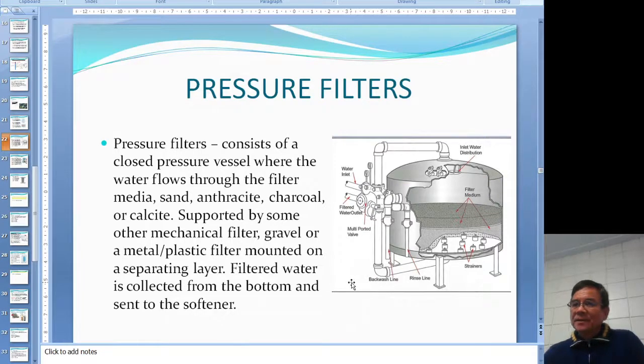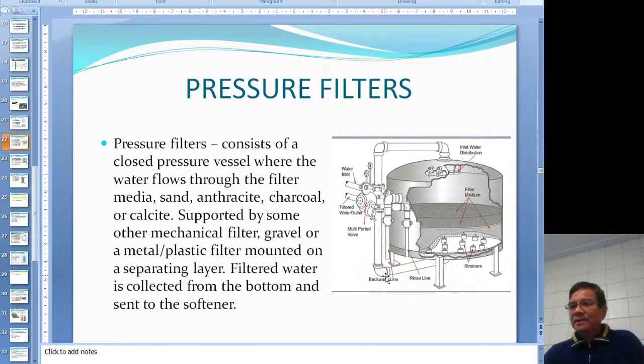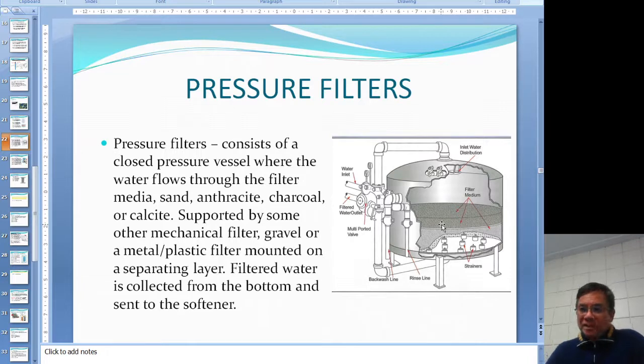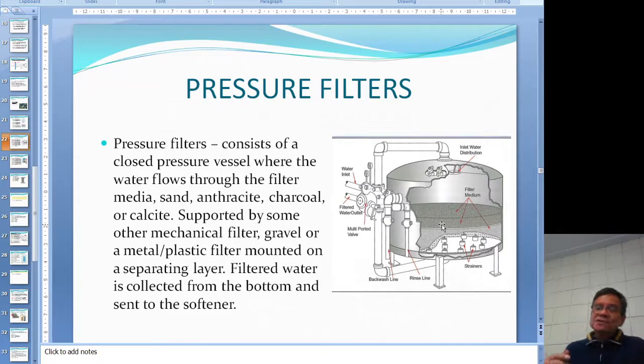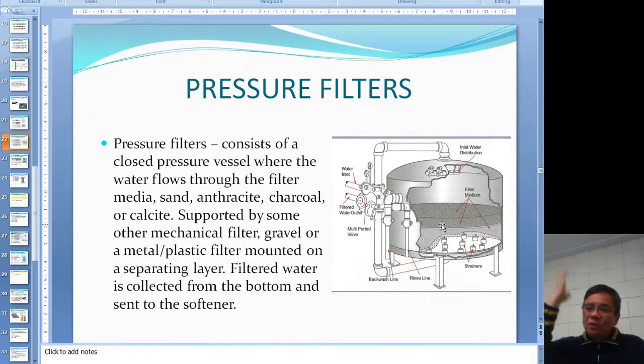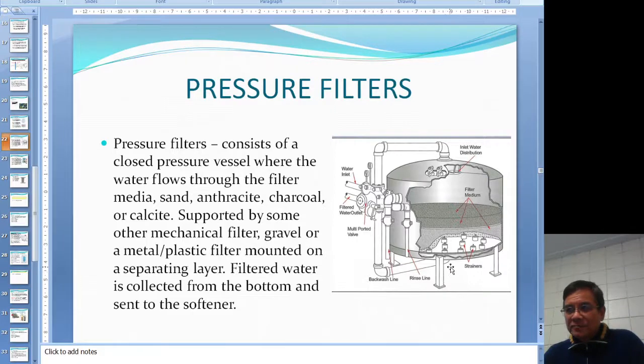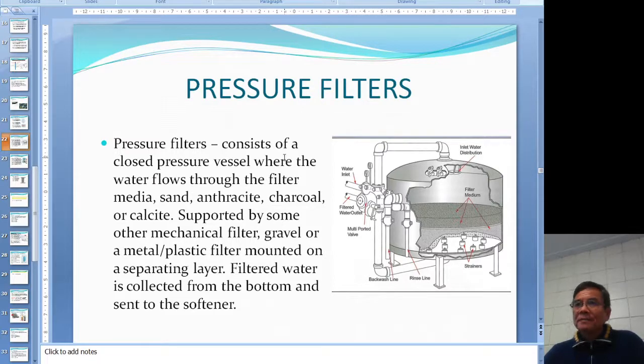The water comes in from the top, goes through the filter, collects at the bottom, and comes out there to the softener. After running for a while, the filter layer collects lots of dirt. To clean it you backwash - put water in from the bottom going up to push the lighter material down the drain. This process is called backwash or reverse flow - it removes all the dirt and organic material down the drain. That is how a pressure filter works.